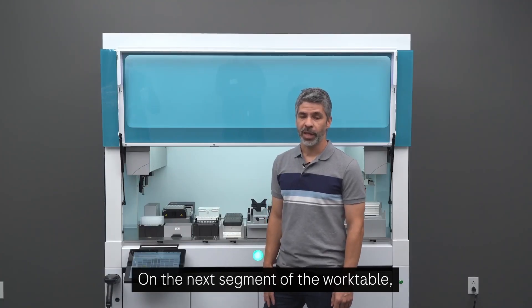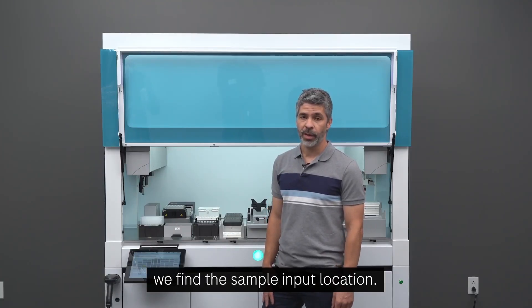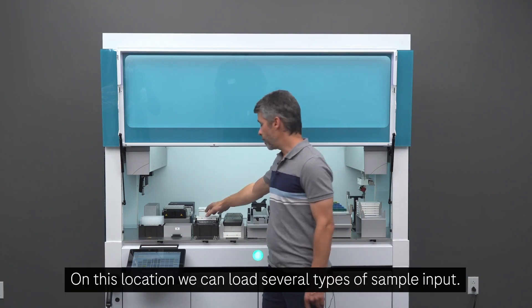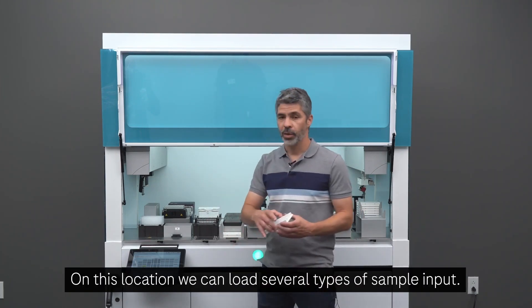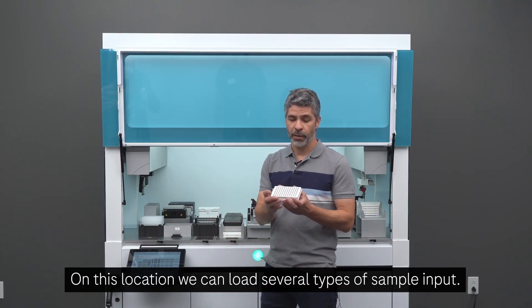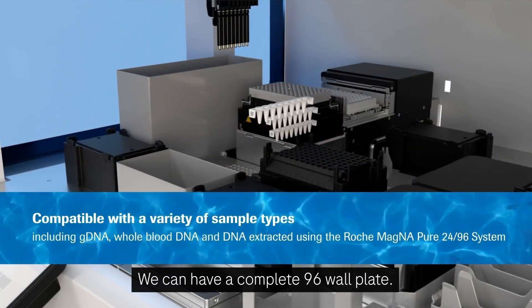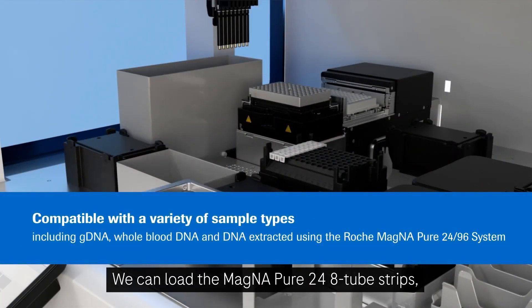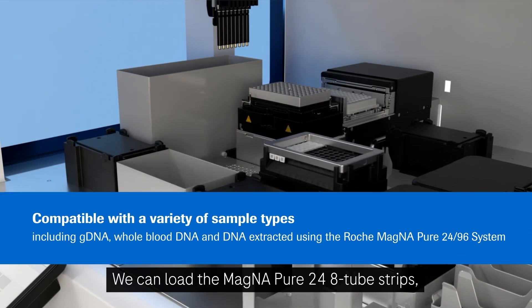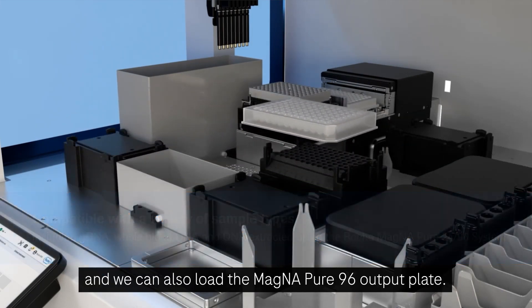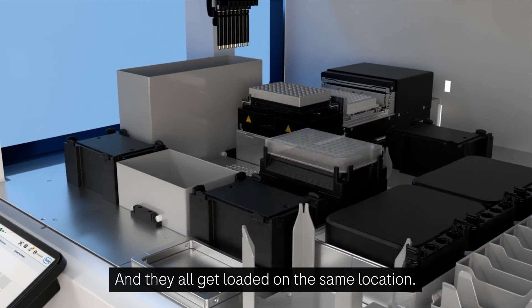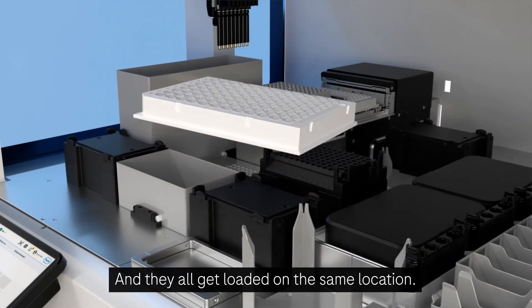On the next segment of the work table, we find the sample input location. On this location, we can load several types of sample input. We can have a complete 96-well plate. We can load the MagNA Pure 24 8-tube strips. And we can also load the MagNA Pure 96 output plate. And they all get loaded on the same location.